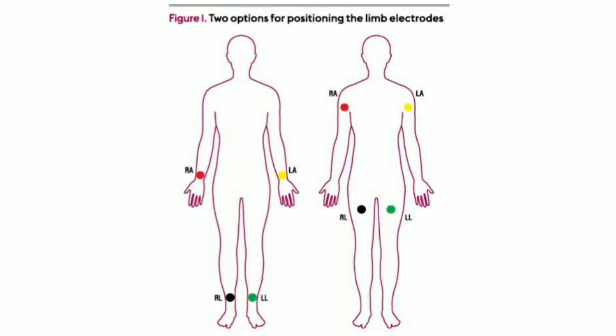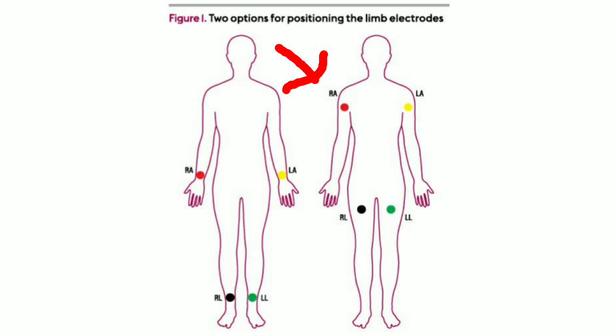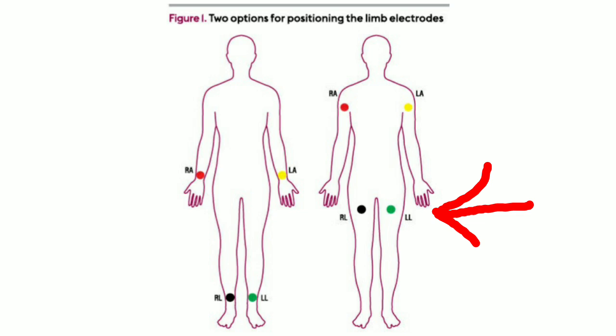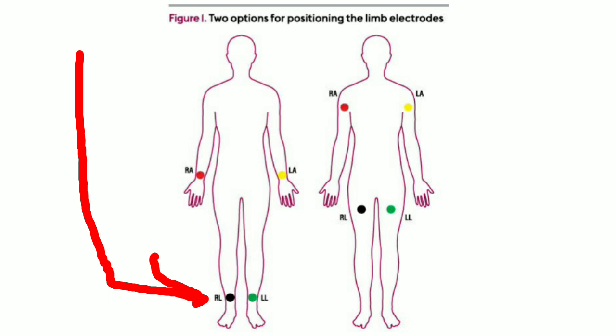Using the mnemonic: R — the red electrode is placed on the right wrist. Y — the yellow electrode is placed on the left wrist. G — the green electrode is placed on the left ankle, preferably due to less muscle mass there. B — the black electrode is placed on the right ankle and serves as an earthing/ground lead, so it is not involved in making ECG recordings. That leaves three effective limb leads.